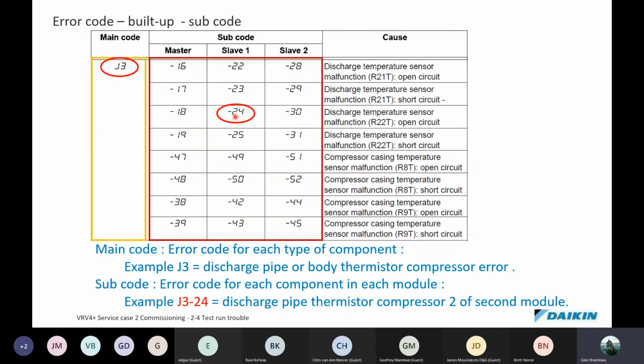Right, here's something that you need to also keep in mind about slave 1 and slave 2. If you're standing next to a configuration of 3 condensers with a master, slave 1 and slave 2, the slave 1 is actually not the condenser that is next to the master. It's actually the furthest condenser away. Okay, so just keep that in mind when you're fault finding as well.